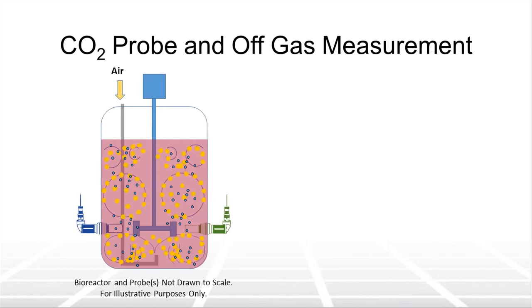CO2 probes utilize pH probe technology by surrounding the pH probe with a bicarbonate solution that is separated from the media via a hydrophobic membrane. That membrane allows CO2 to diffuse across it and into the bicarbonate solution, and relay the CO2 levels to the bioreactor controller.